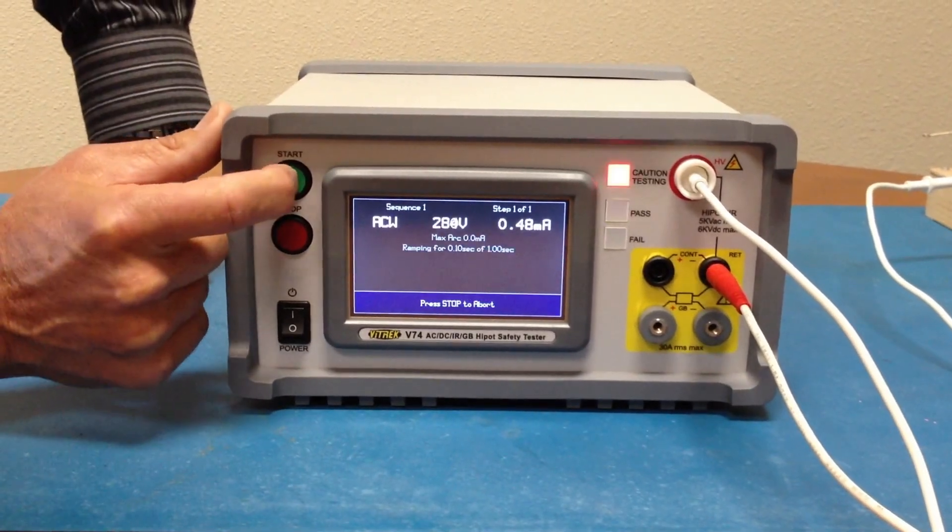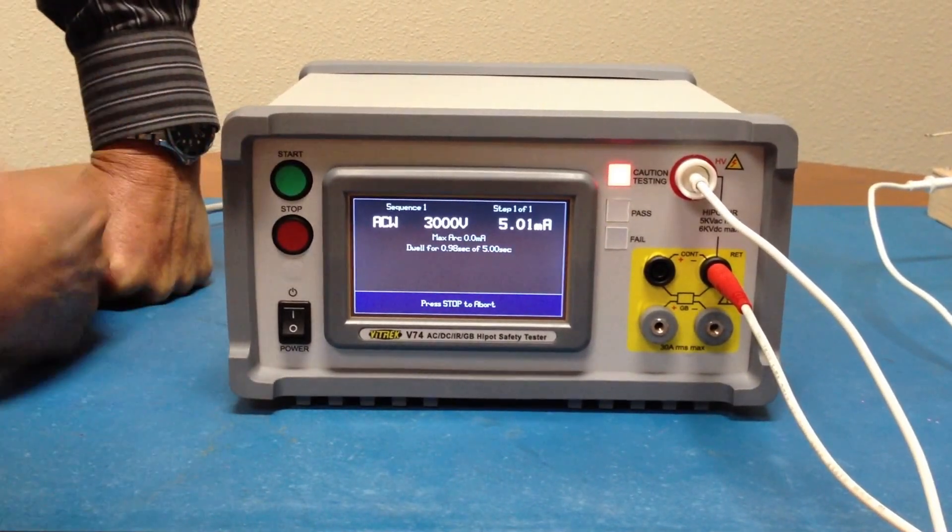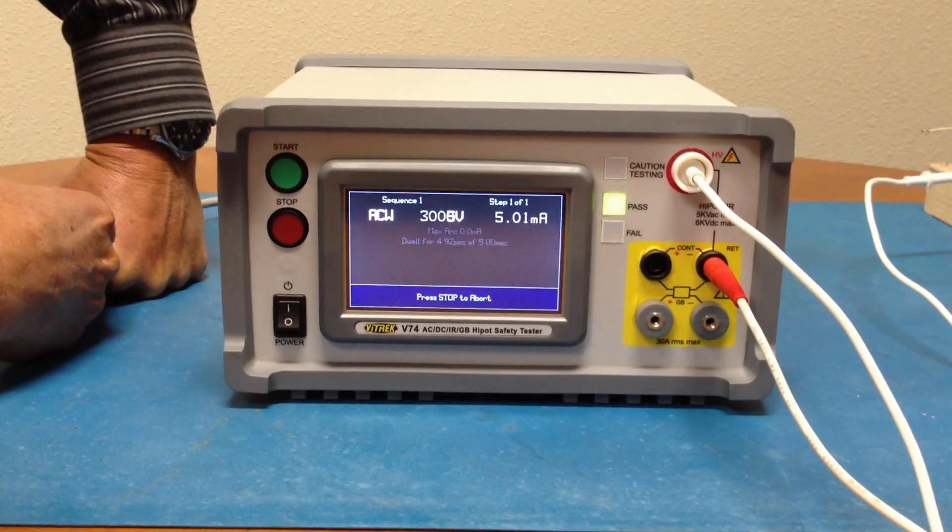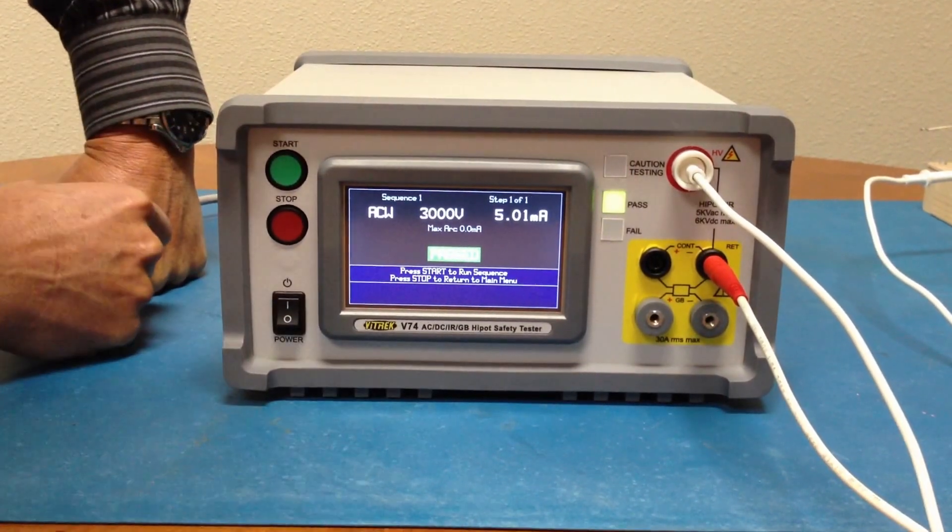We're going to run this test. We've got a load set up here. We're running a 3,000 volt test into a 5 milliamp load and we have passed the test as indicated.